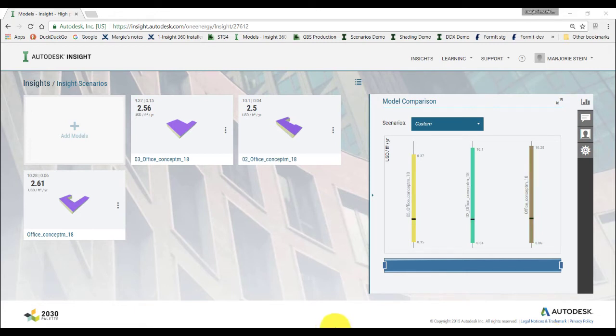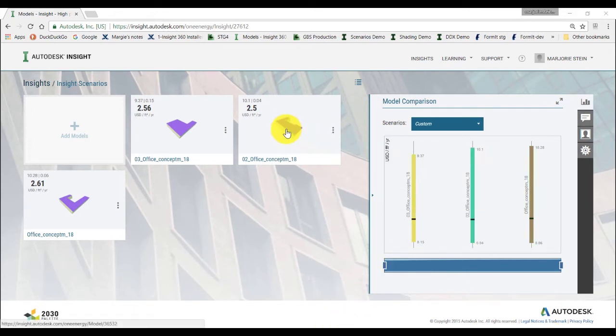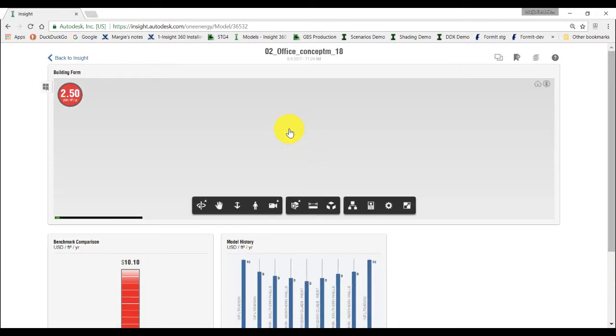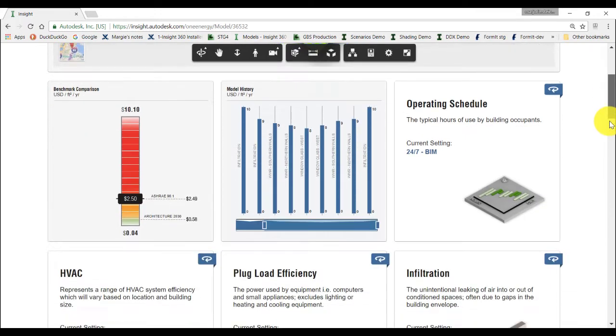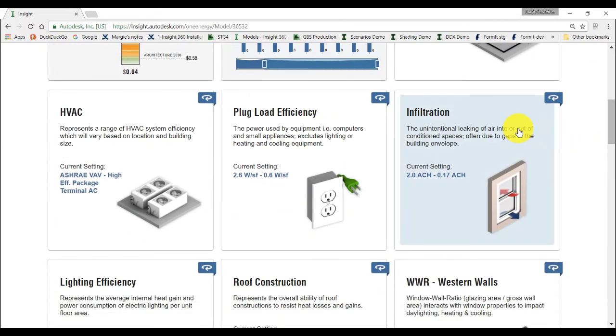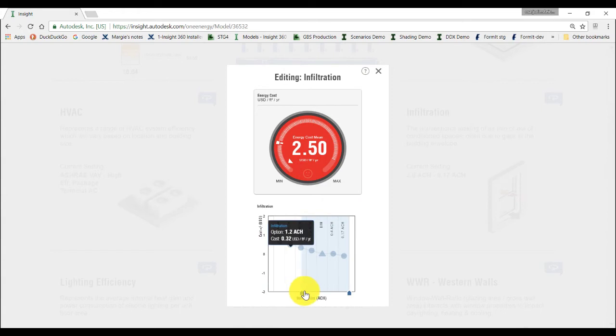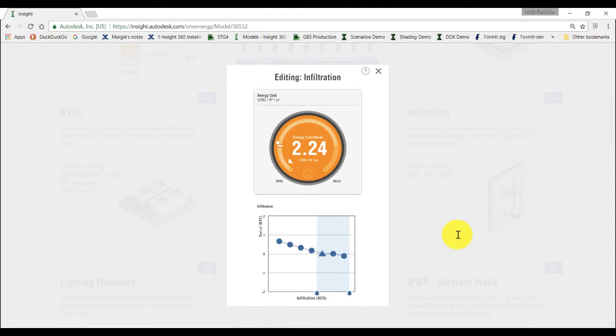To create a scenario, click on the model to open the page with factor widgets and edit the factors to reflect our desired settings. We want to see how infiltration and window to wall ratio affect our model, so change these factors as shown here. Open the infiltration widget and choose a range from the baseline model setting to a more airtight setting of 0.17 air changes per hour. Notice how the color of the energy cost range dial changed from red to yellow, indicating we are moving toward a higher performance building design.